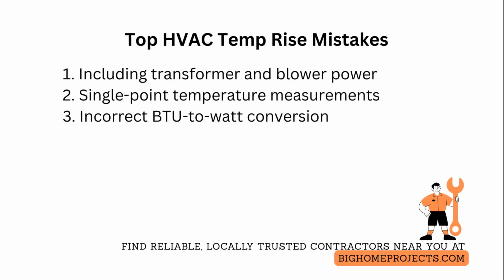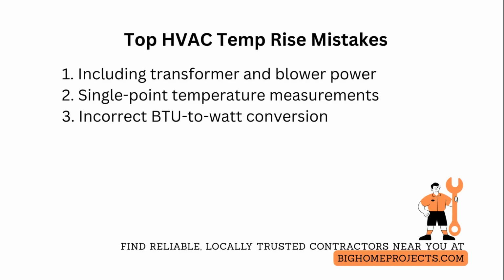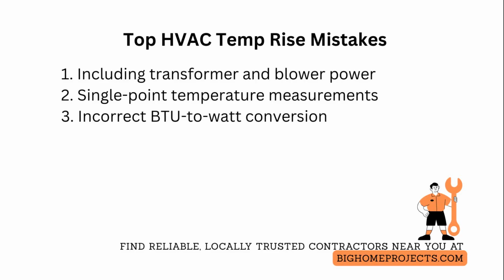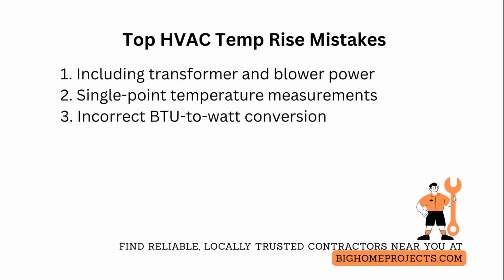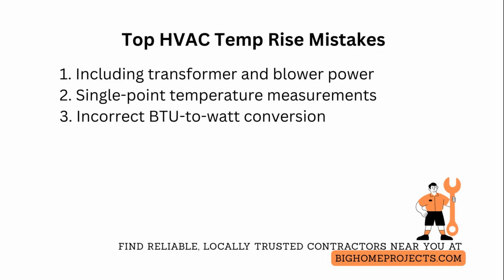One of the biggest mistakes is including transformer and blower amperage in the airflow calculation, which inflates watts and gives a falsely high CFM. Fix this by isolating and using only the electric strip heater's measured watts or the rated heater watts from nameplate data.